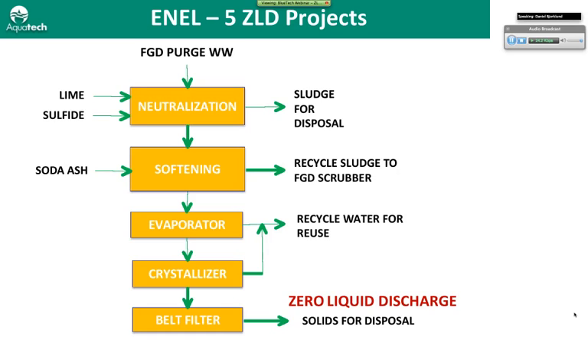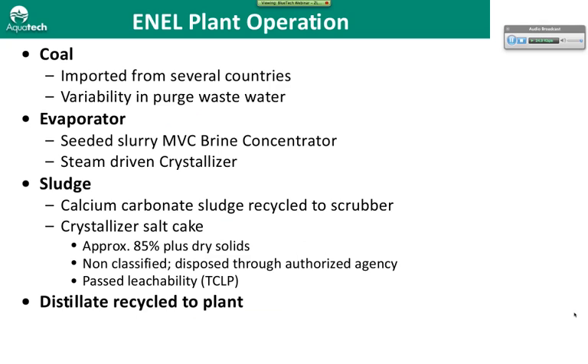If we look at a typical configuration that has been operating for several years, we take the FGD purge wastewater, which is very high in calcium chloride, and we bring it into a lime neutralization clarifier along with sulfide. We're neutralizing the wastewater and also precipitating heavy metals, and then we add soda ash, which precipitates calcium carbonate, and as a result you end up with a sodium chloride or sodium-based chemistry to the evaporator crystallizer, which operates now more traditionally in dewatering equipment.